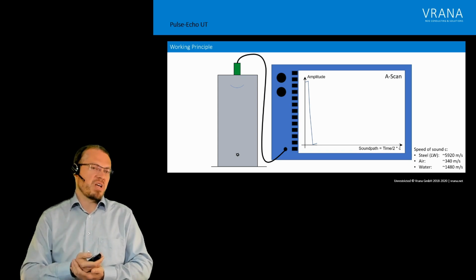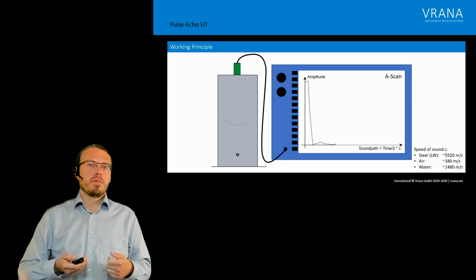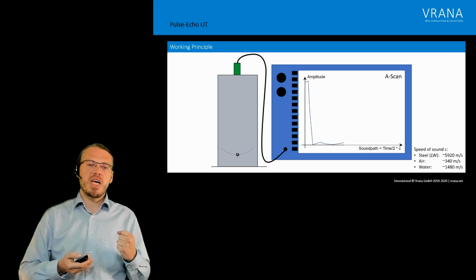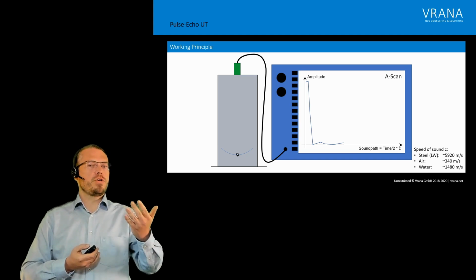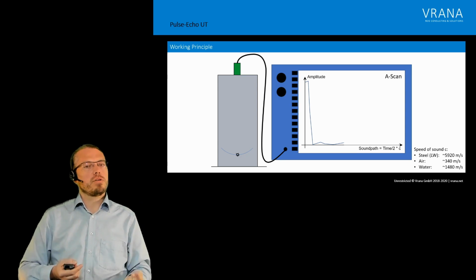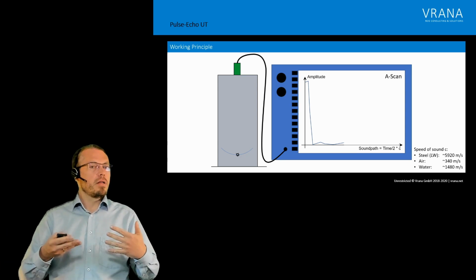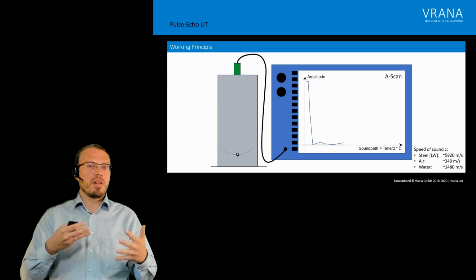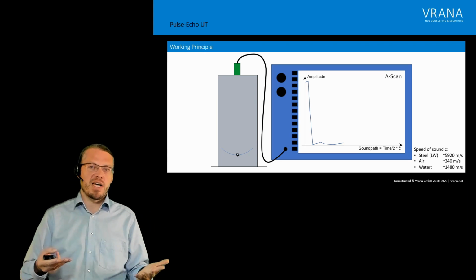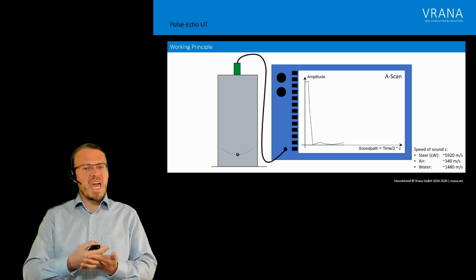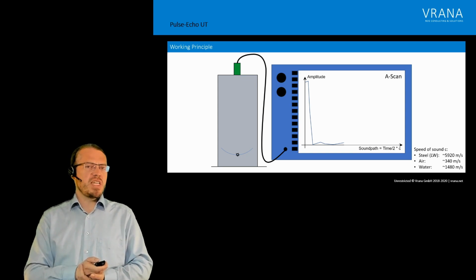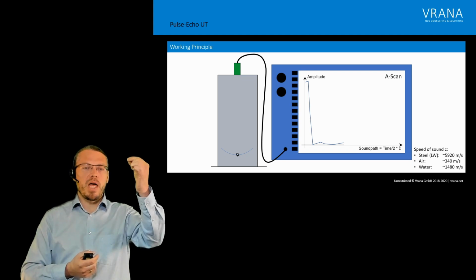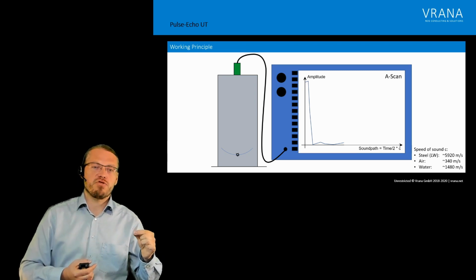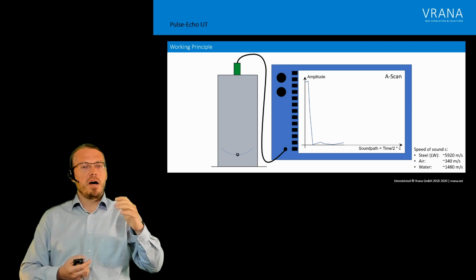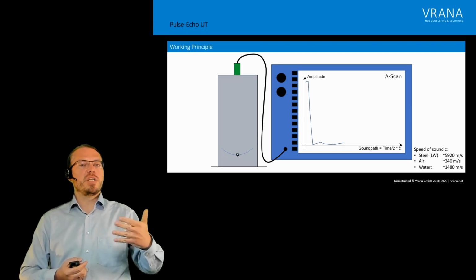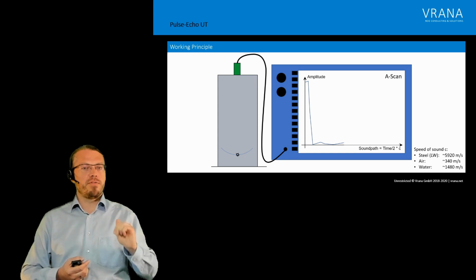Here we see where our wave is at this moment of time. It's traveling further, traveling further. Now it's hitting our defect. If we look onto our screen, to the top we are seeing the amplitude, and to the right we are seeing the time our sound needed to travel, or we can also calculate that into a sound path by applying the speed of sound. If we look onto that so-called A scan, why do we not see that indication right now? It's pretty simple, because that wave just traveled to the indication, but it also has to travel back from the indication to the surface so that we can see it. All we have seen up to this moment on the A scan is the dead zone in the beginning, and then some noise from the first half of our component.